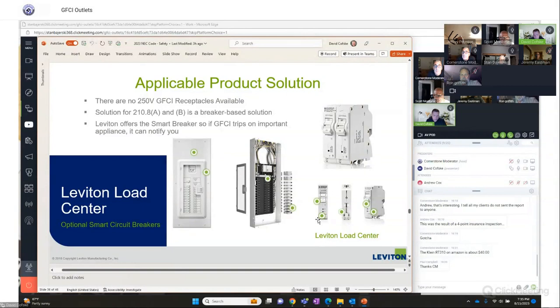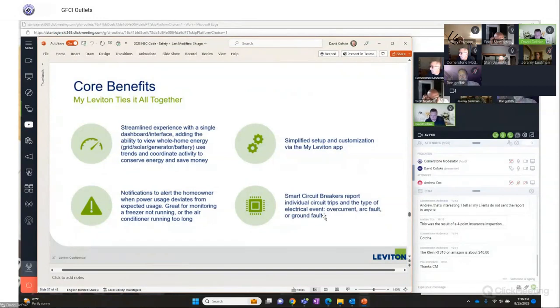Now on these bottom breakers, these look like dual function because there's two lights. A single GFCI or a single AFCI circuit breaker will have one light on it, and the two light units are usually dual function or combination breakers. But next to the light, there'll be a little symbol that'll say AF for arc fault or GF for ground fault. So it's really easy to detect what that breaker is.